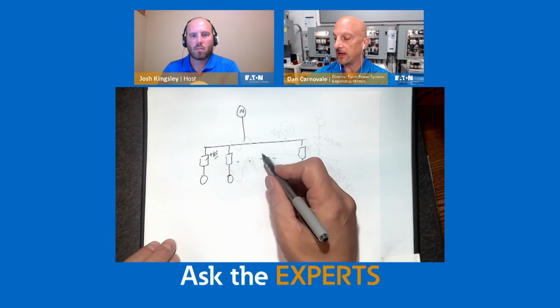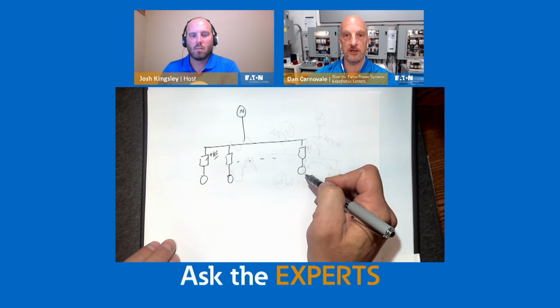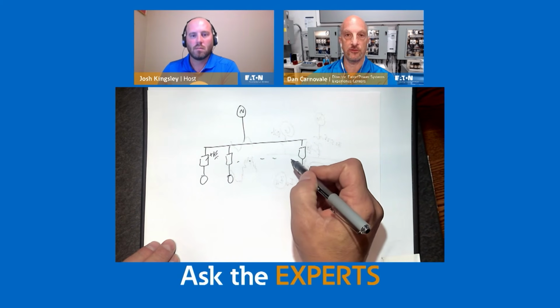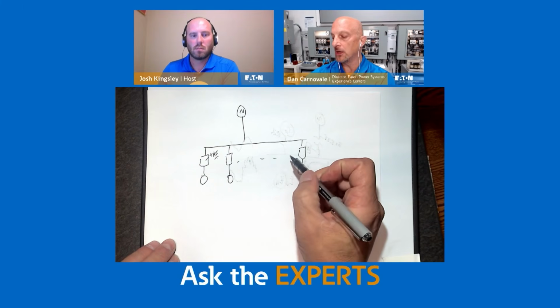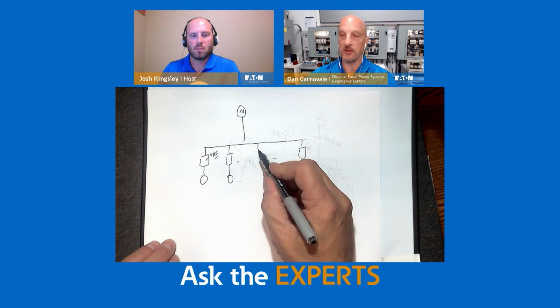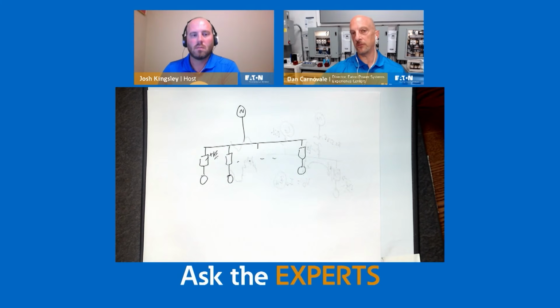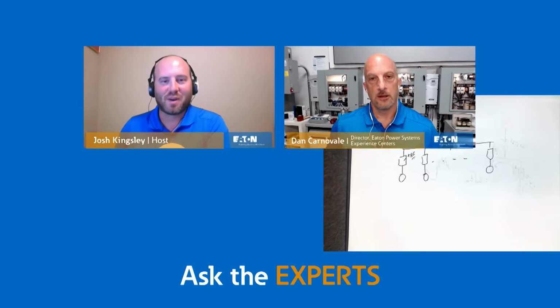Now, what if you had 5 drives that are running all the time and 5 redundant ones? Well, you basically have 5 filters that are sitting there with nothing to do half the time. So now that might be where a system level, like an active filter, comes in. Even if an active filter costs more to begin with, you might put it on a system level and still be able to deal with the problems on many drives instead of one drive. I don't know, Josh, if that helps to clarify it a little bit better. So the real question is, do you want to put the active filter in, put the extra cost up front, or do you want to do it in service calls, adding an active filter to somewhere between 5 and 10 drives if you've got redundant ones in that particular situation?